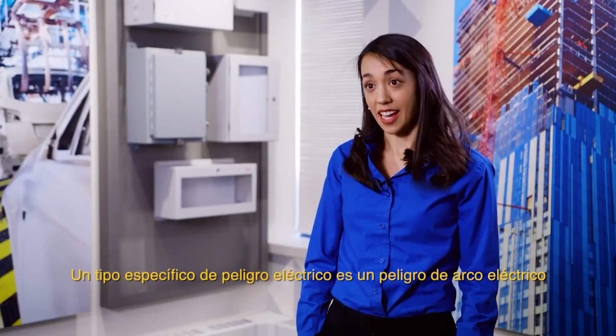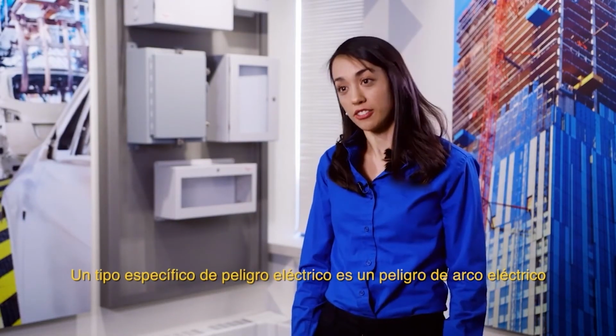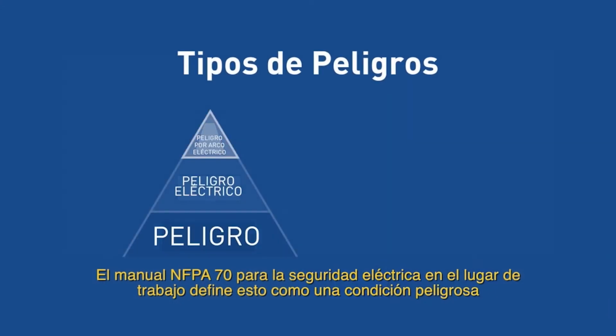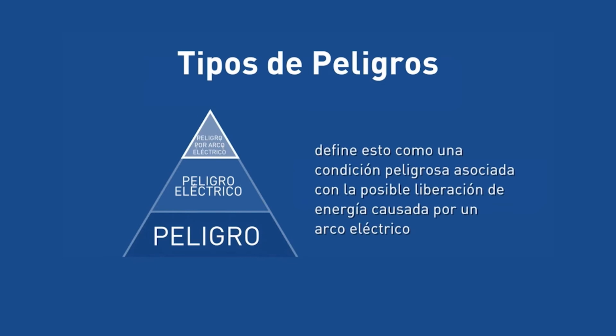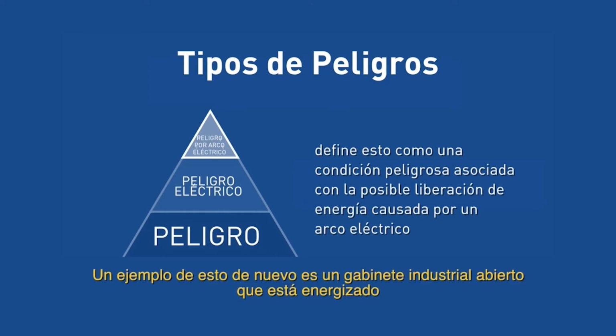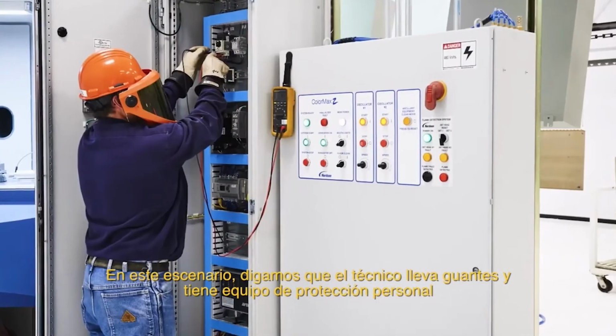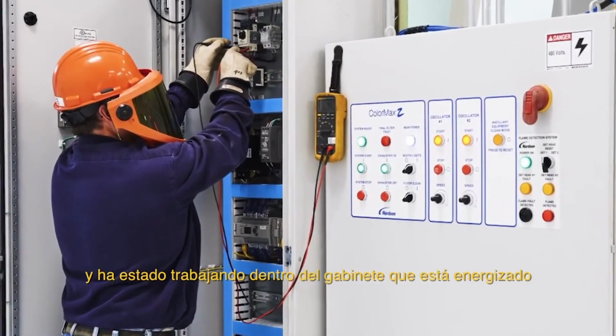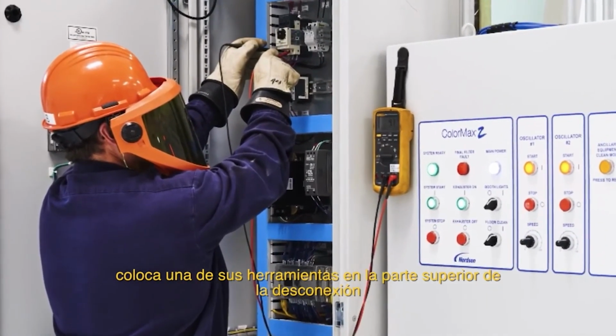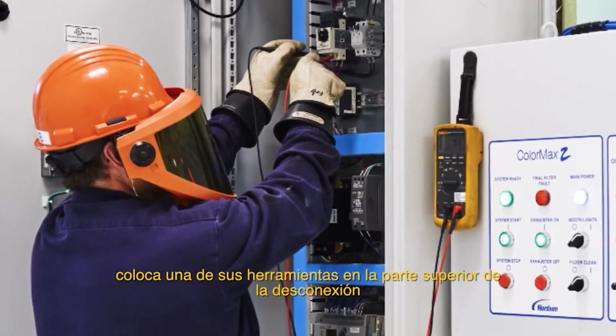A specific type of electrical hazard is an arc flash hazard. The NFPA 70E Handbook for Electrical Safety in the Workplace defines this as a dangerous condition associated with the possible release of energy caused by an electric arc. An example of this is, again, an open industrial enclosure that is energized. In this scenario, let's say the technician is wearing gloves and has PPE, and as he's working inside the enclosure, which is energized, he places one of his tools on top of the disconnect. If this tool comes into contact with the disconnect lugs, that could create a short and cause an arc flash.